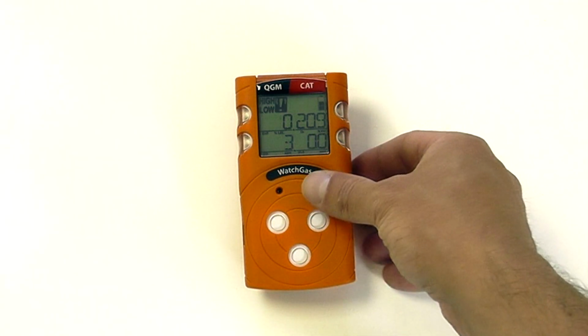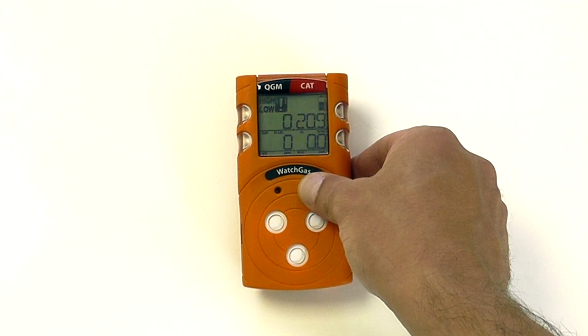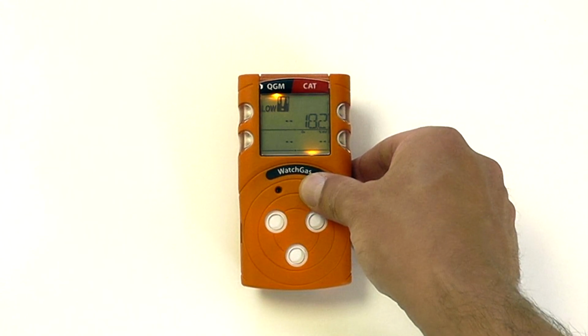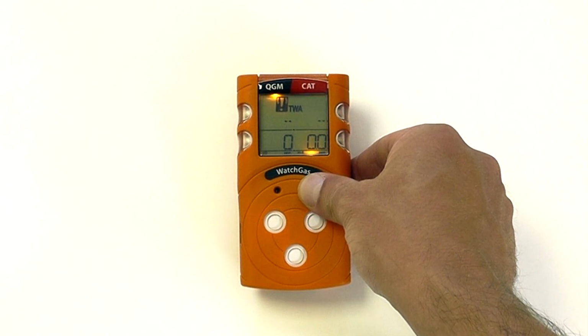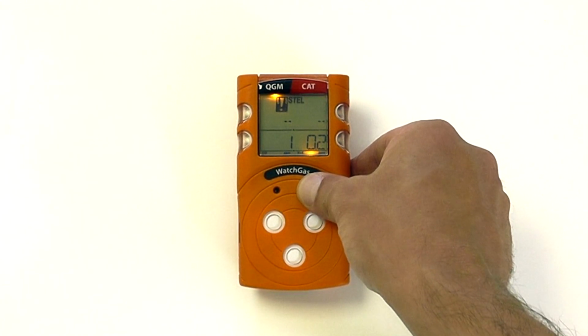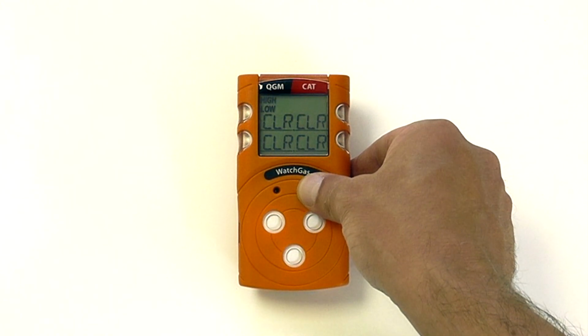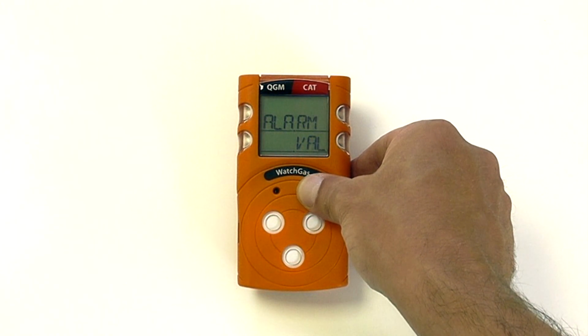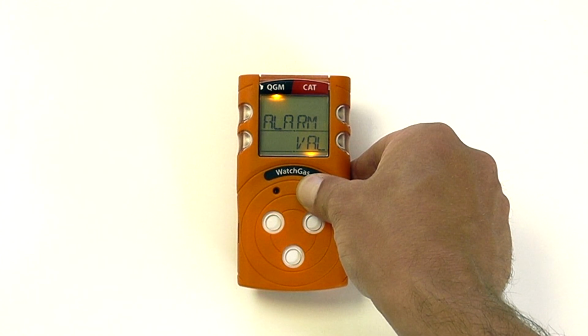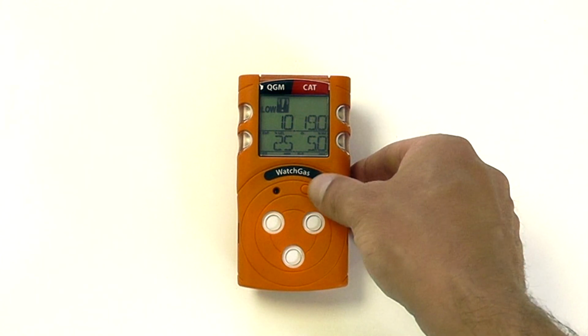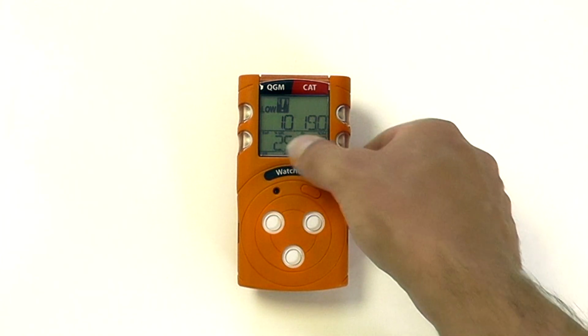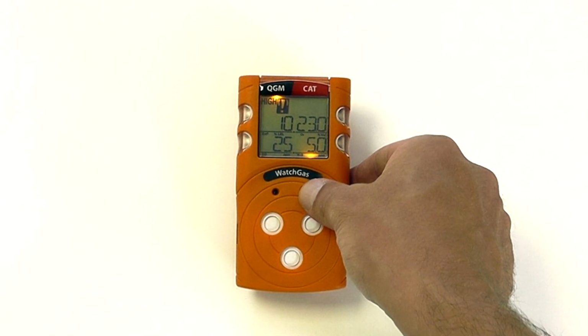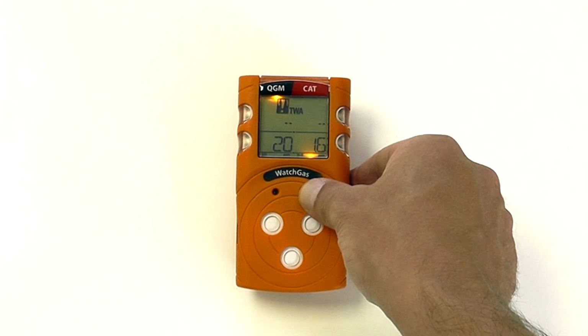General operation of the unit is to scroll through some of the measurement criteria. You can press and look at our high limits, our TWA values, our STEL values. We can clear any of our high, low, STEL and TWAs. We can adapt our alarm values. We'll take a look at our alarm values by pressing and holding. So we can see our low alarm value, our high alarm value, our TWA and our STEL values.